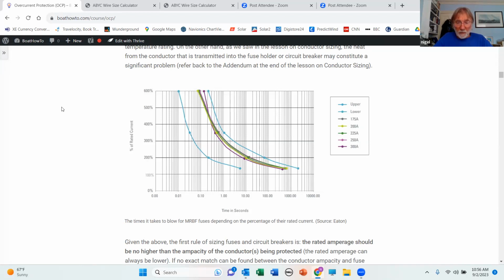In practice, what we want on those circuits are ANL fuses, which come in a holder that's about this big. They're not terribly expensive, and they have an AIC rating of 6,000 amps. So they're good for pretty much any lead acid battery bank up to a pretty decent size. So just stick an ANL fuse on there, maybe $20. When we get to larger battery banks, we need something with a higher AIC rating.